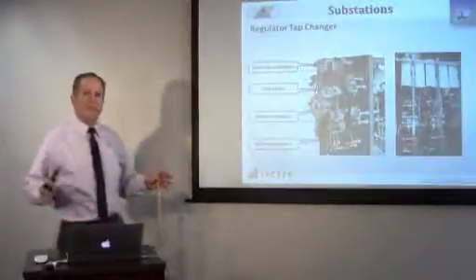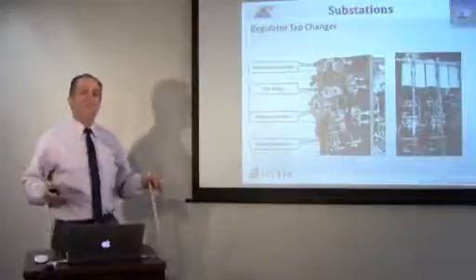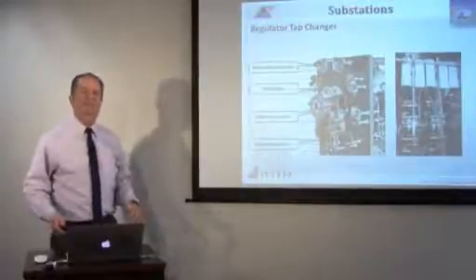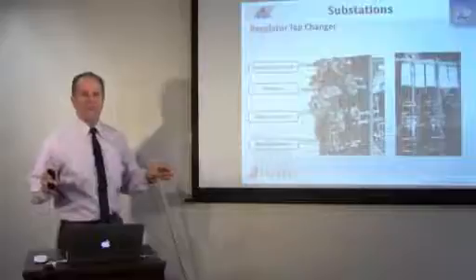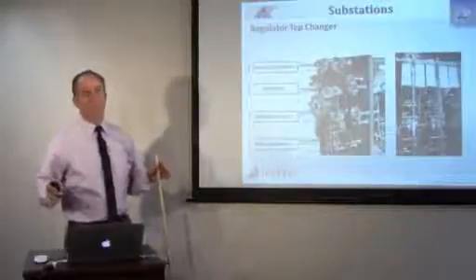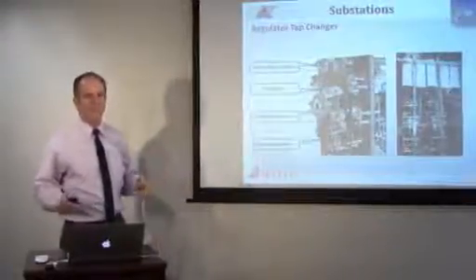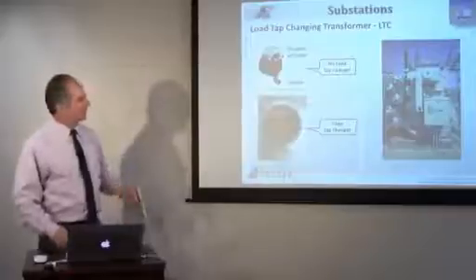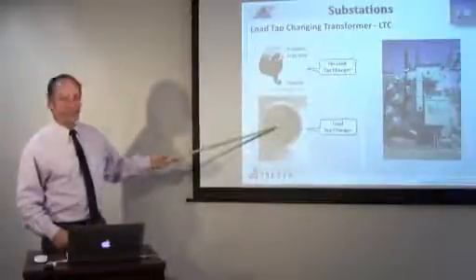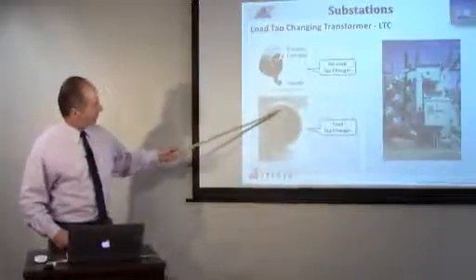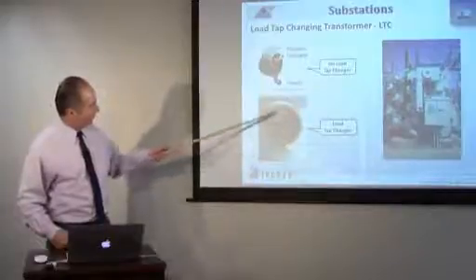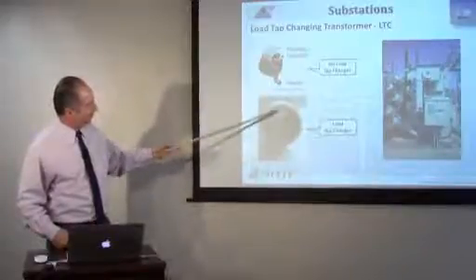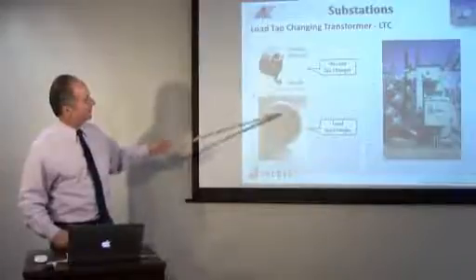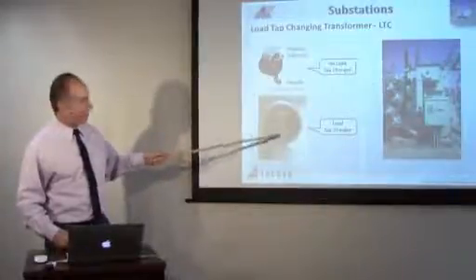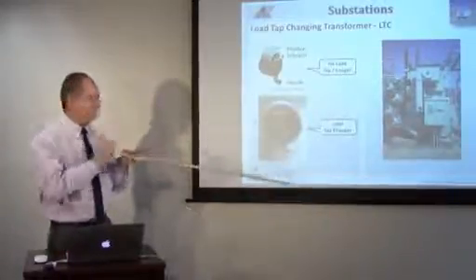So what are voltage regulators used for? To regulate the distribution voltage so that services stay within 120 volts plus or minus 10%. Okay, here's what a gauge looks like on a regulator. Here you go, plus 16, minus 16 with neutral in the center. Okay, this is a load tap changer because it makes before breaks.